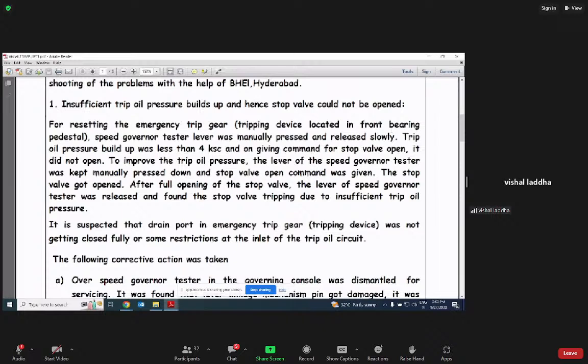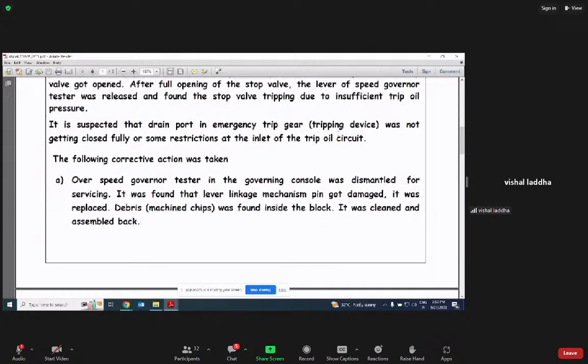After full opening of the stop valve, the lever of the speed governor tester was released and the stop valve was found tripping again, because manually we were pressing the overspeed device. That is why trip pressure had built up and the stop valve opened. But after removing the manual intervention, it got tripped again. So corrective actions were taken. First corrective action: the overspeed governor tester, this is OTT, in the governing console was dismantled.